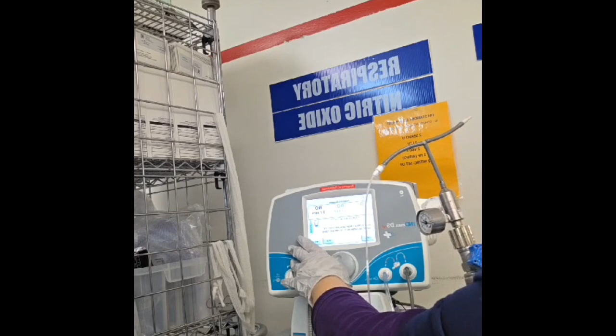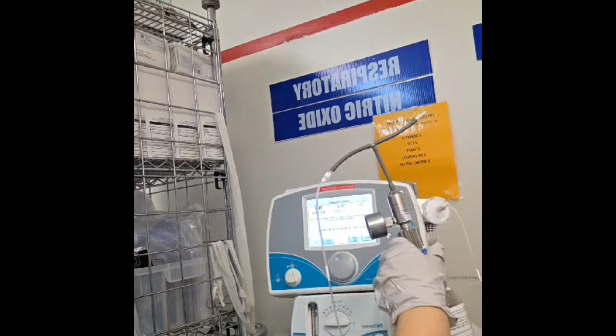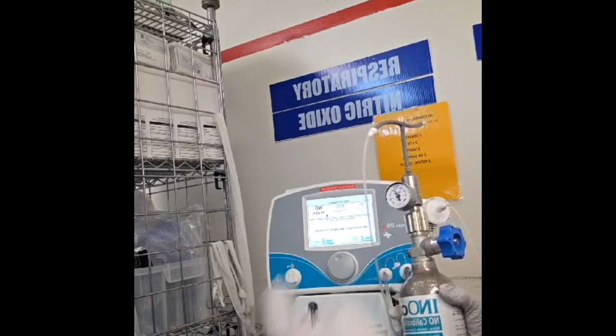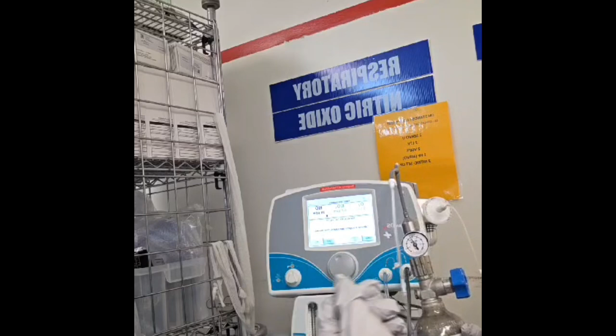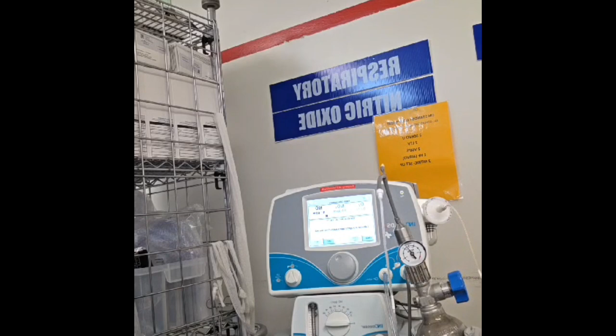Everything's connected, regulator, everything's connected. I removed the sample line. I'm gonna turn it on. I have to turn on my tank. All right, my tank is on, nitric oxide, my sample line is connected, and I'm gonna start calibration. And this calibration takes about 3 minutes. All 3 tabs, nitrogen dioxide, nitric oxide, and our oxygen, all take approximately 3 minutes to calibrate, okay? It's pretty easy. I will come back to you when it's almost done so you can see what it looks like, okay? All right, bye.